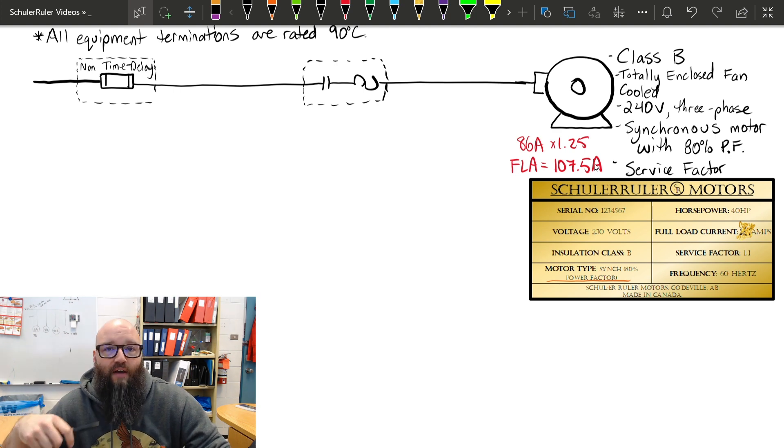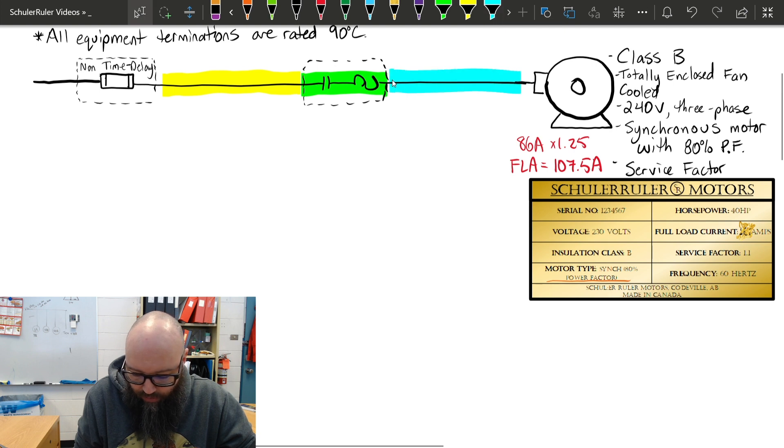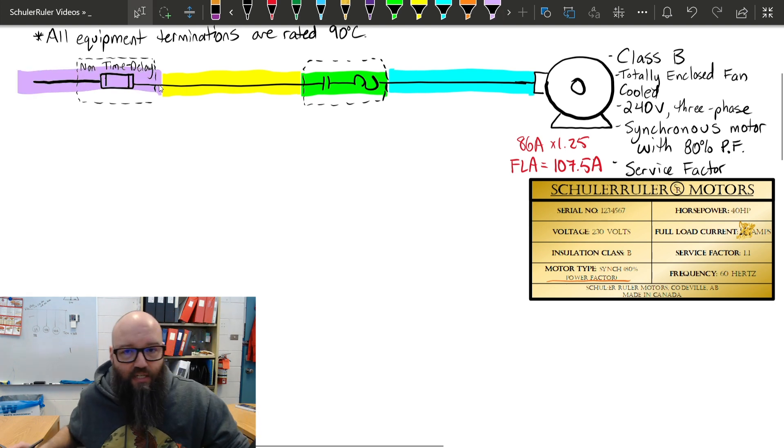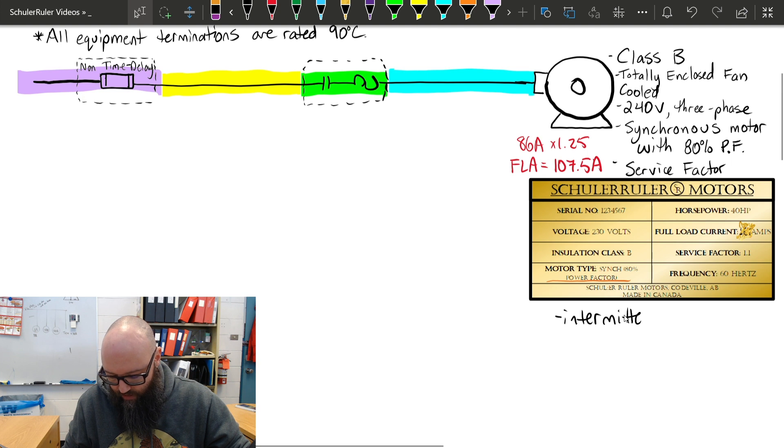We're going to use that for all of our different calculations: our overloads, our branch circuit conductors, our motor supply conductors, and eventually our overcurrent protection. So let's start off with our branch circuit conductors. I'm just going to highlight these individual sections so we have points of reference. For the duty cycle in this motor, we're going to use intermittent duty, operating for a five-minute time period.